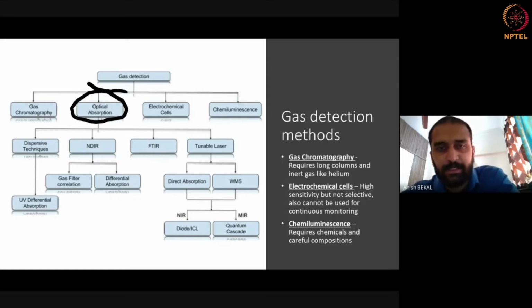There is something called gas chromatography, where you actually mix the gas with a lighter gas like helium, and then pass it through long glass tubes, where all these gases separate out, and you can measure individual gases. That requires a very cumbersome chemical method, which was used quite often before optical technologies became available. Even now, for example, standards in the US require you to compare your optical instrument with a gas chromatography instrument. And even now, when you make cylinders, you basically use gas chromatography to check the concentration. So that is one method.